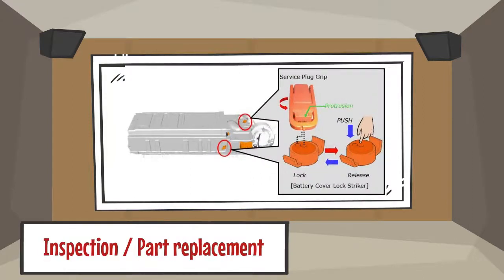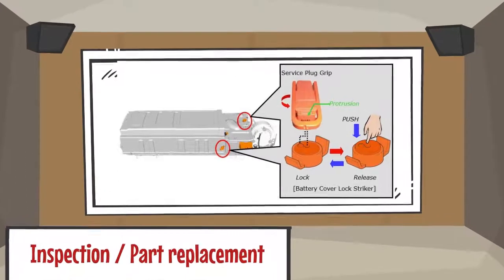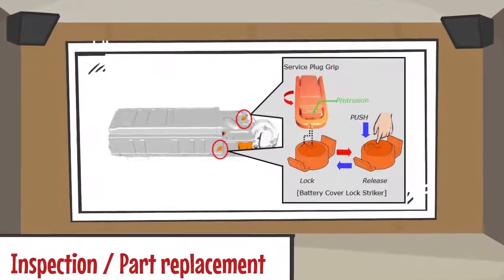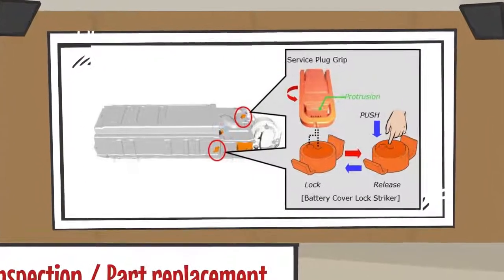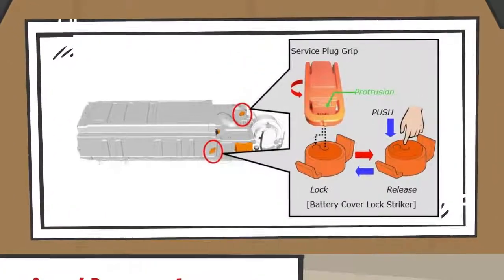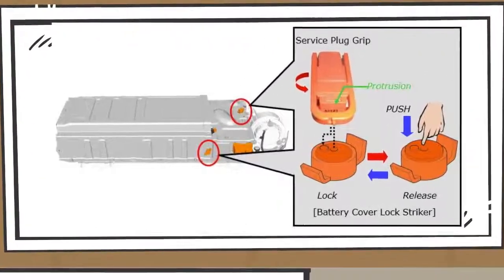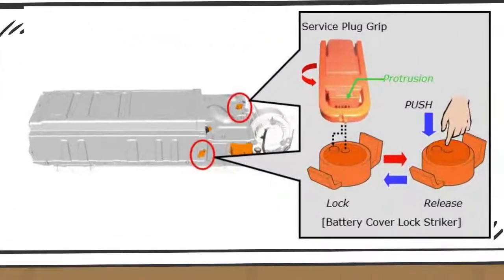If the lock of battery cover lock striker is not released, the battery cover cannot be removed. The battery cover lock striker prevents the technician from removing the battery cover without removing service plug grip. Use the protrusion on the service plug grip to release the lock of battery cover lock striker.